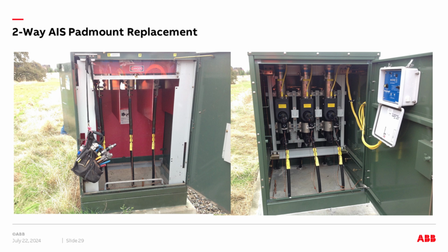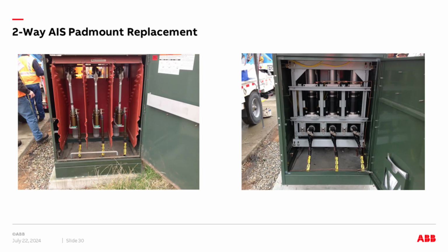I can show in the next slide one side before and after. So the cables were live front terminations, so those were cut and then terminated with elbows that were then plugged onto the bushings in the solid dielectric gear on the right side. And then this is the back side of the gear. You can see on the air-insulated side where the fuses are, and then on the right side again the elbows plugged into the single phase interrupters on that side.